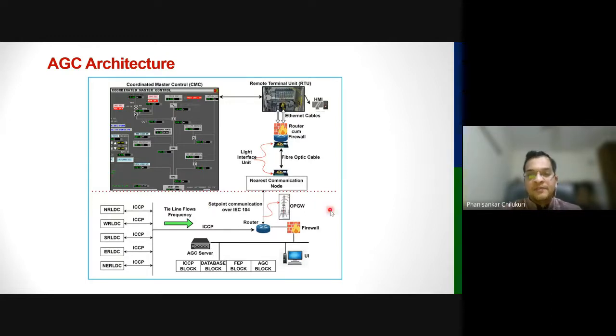Through the optical fiber ground wire network, the signal reaches the nearest communication node, and we have fiber optic cables laid till the control room of the unit, and there is a remote terminal unit dedicated for AGC. That remote terminal unit is wired with the digital control system of the power plant. This digital control system of the power plant exchanges a lot of signals with the NLDC software every 4 seconds, and the NLDC software provides signals to the DCS every 4 seconds.